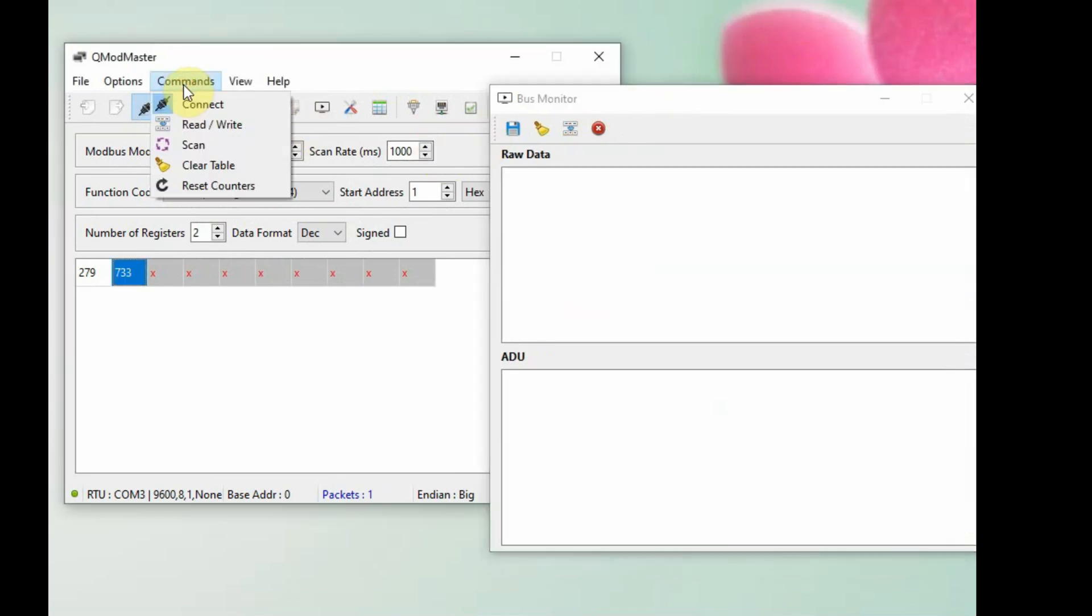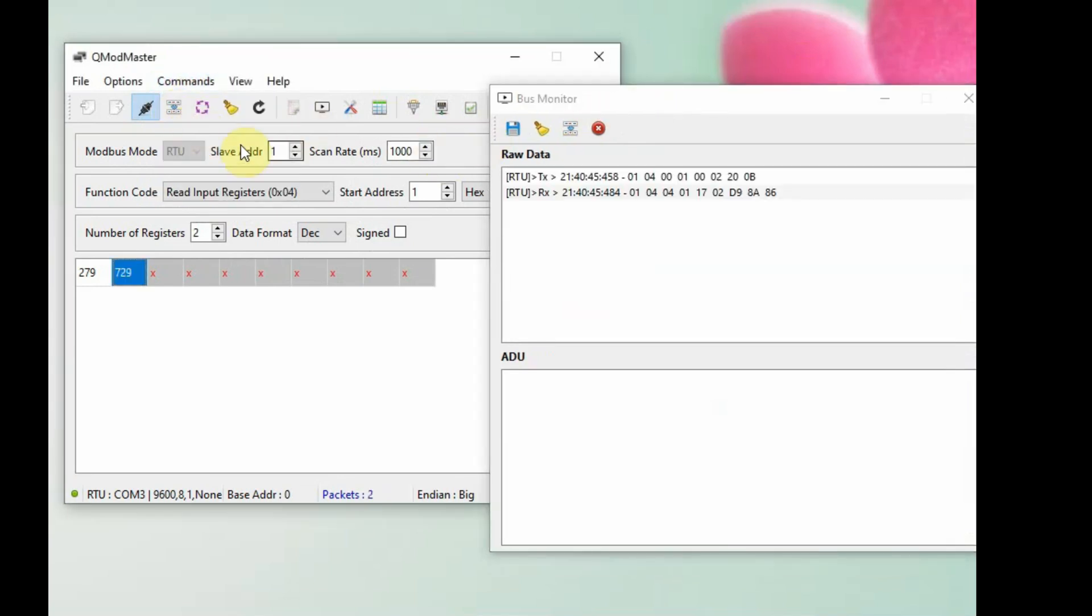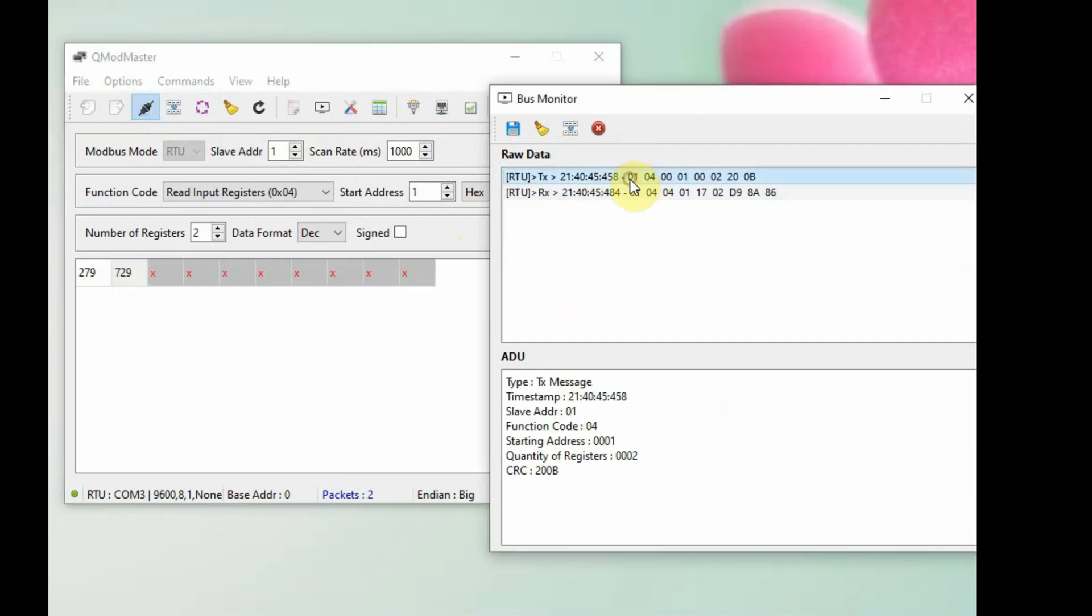The query is 8 bytes. We are sending 0104 starting address, and 0002 is the number of registers we are going to read. The final two bytes are CRC error check. The response is 9 bytes of data.